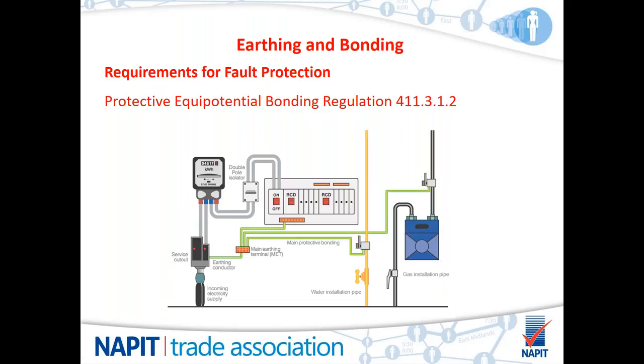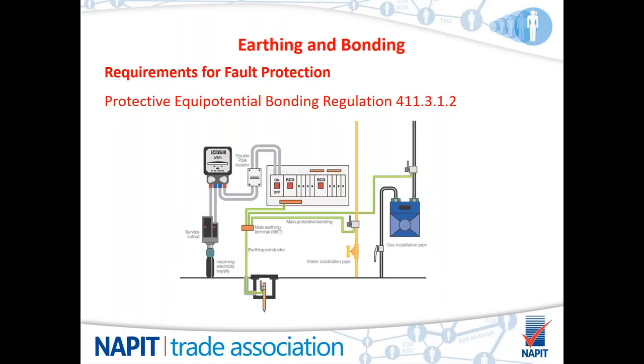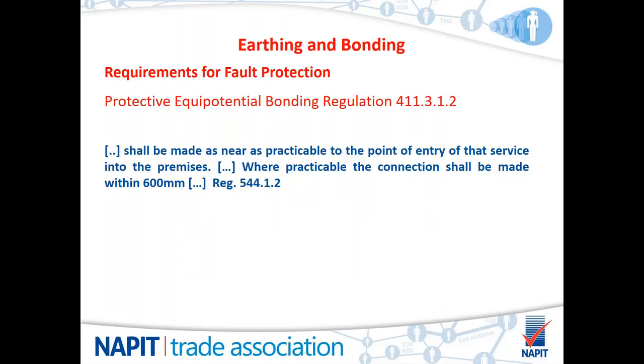There may be a charge, but that would be upon the DNO to decide whether there was a charge for connecting to a PME system. And with PME, it is always advisable to look for the labels on the service cutouts that state there is a PME available. And the final earthing system then, so this is a TT system, which again would be identifiable via the earth spike. Now, TT systems you'll more commonly come into contact with in agricultural installations or more rural locations.